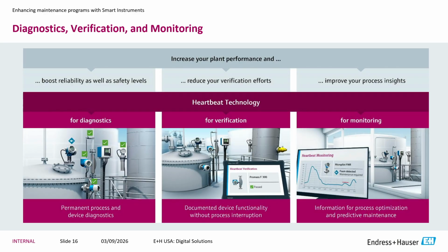A thermal mass flow meter has a very high tolerance RTD. A mag meter has some electrical references based on Faraday's law. Coriolis has incredibly high tolerance crystals inside that act as oscillators at a known frequency. If we're monitoring all that data in real time against these reference points, we can start to make inferences about what the device is telling us.